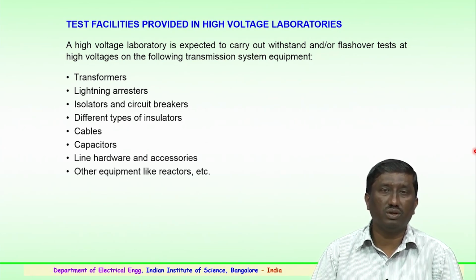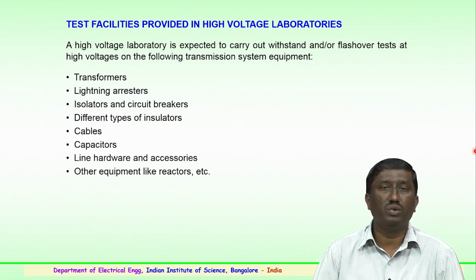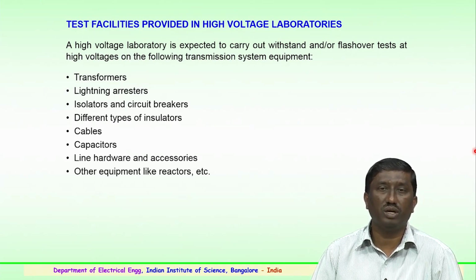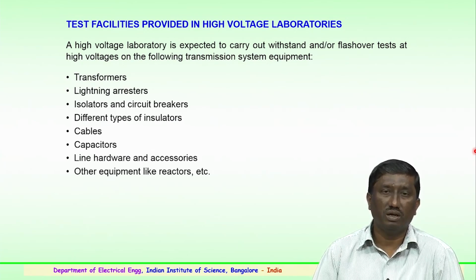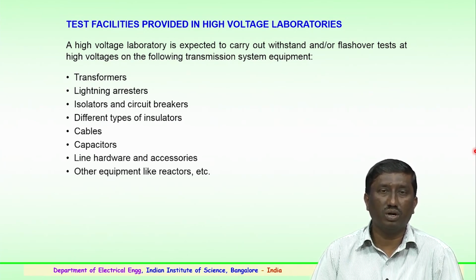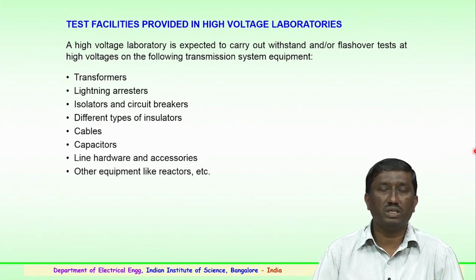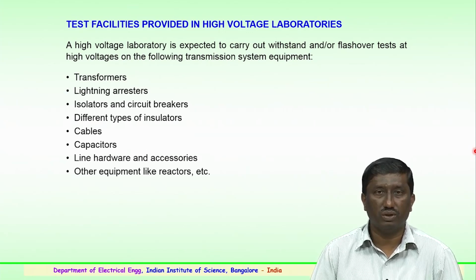Apart from that, there are tests on isolators and circuit breakers, different types of insulators, ceramic, porcelain, glass or polymer insulators, various types of cables, capacitors, and tests on line hardware like the corona control rings, yoke plates, and various accessories, such as mid span compression joint, repair sleeve, vibration damper, and so on and so forth. Apart from this, some other equipment like reactors are also to be tested in the laboratory. So, any high voltage lab is expected to carry out both withstand or flashover tests and certify these equipment for use in the field.